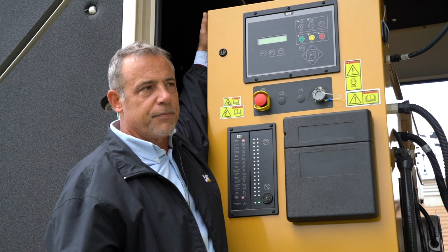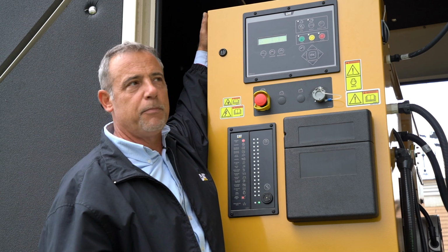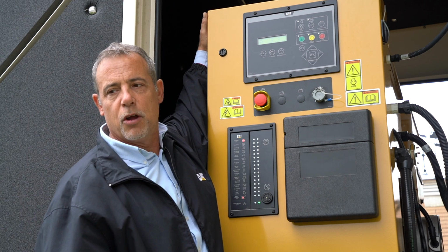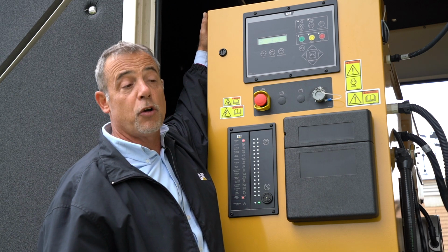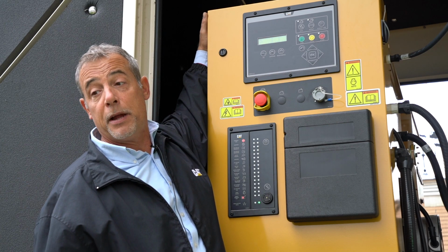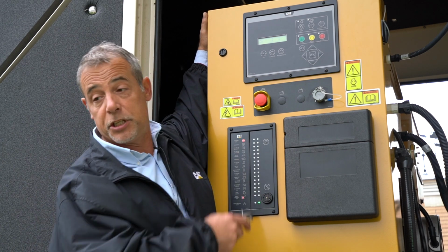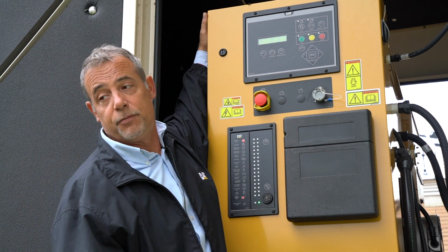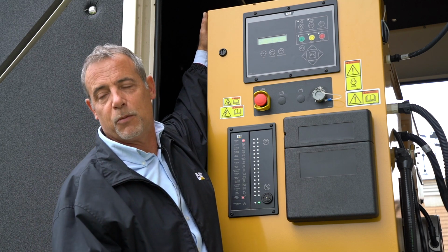But if you were in a factory or something, and you had a lot of motor loads on it, and the utility's charging you more money because they said you have a poor power factor, you could actually run it on the generator and see what it actually is. To fight with them and tell them, yeah, we got a better one than what you're saying.